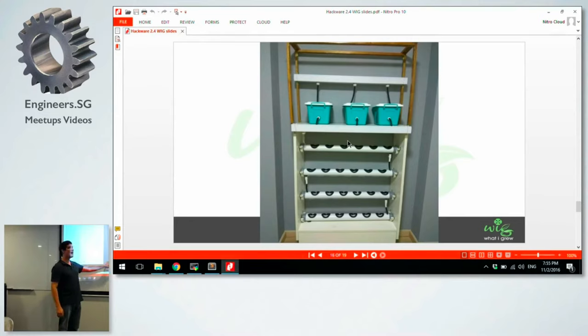So I have one problem here that I would like to see if anyone here can help me with. I've got a couple of solutions that I was thinking of. I've got two pumps. One is from an aquarium, for which the flow rate for this system is correct. It flows at around 8 liters per minute. But it's not strong enough to get all the way up there. And the other one I have is strong enough to get all the way up, but the flow rate is 50 liters per minute. And that means I'm going to flood my place, so I can't use it.